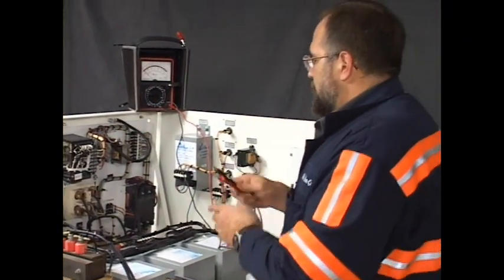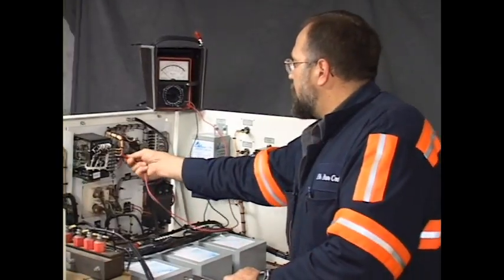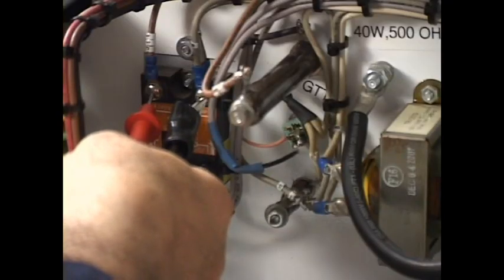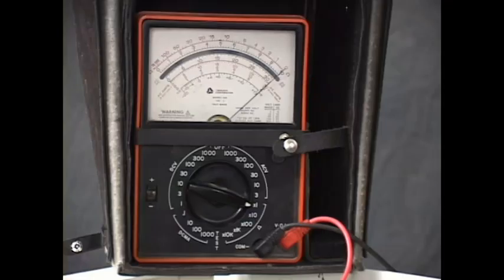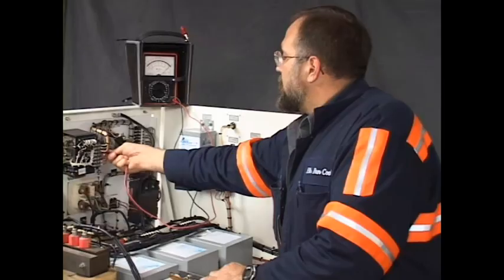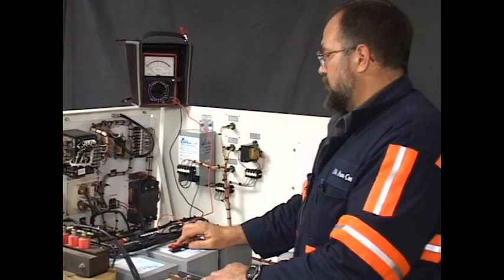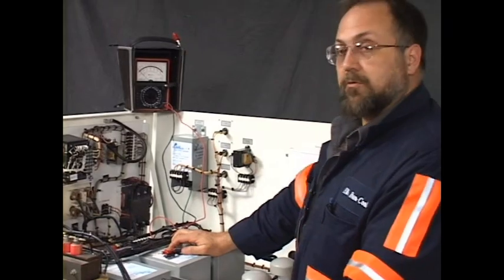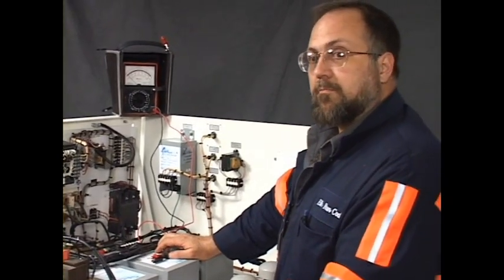Leaves only one. I'm going to put one lead on wire 11 on the GTR and the other lead on wire 8 on the GTR. And as you saw, the needle reads a full-scale continuity. The relay contacts are shorted, and that's our problem.